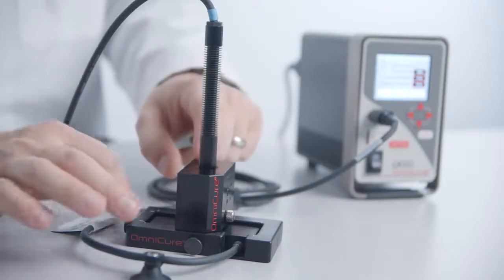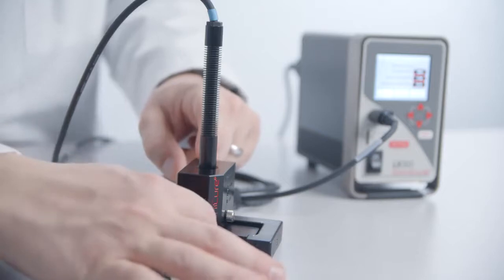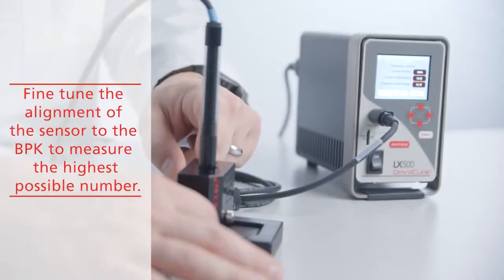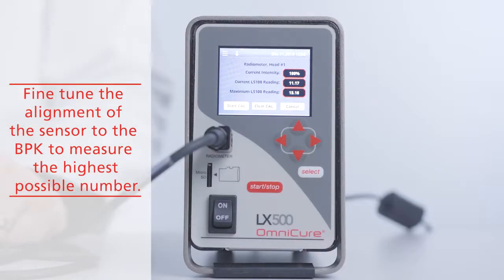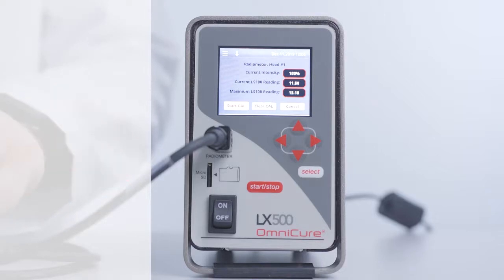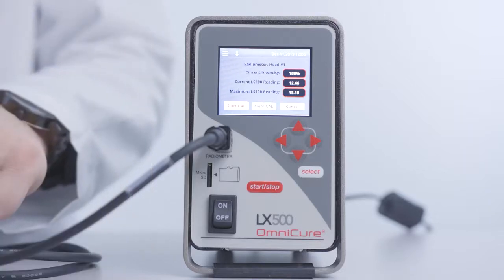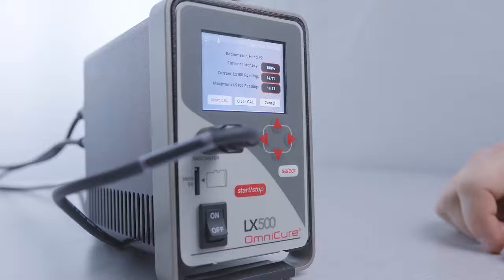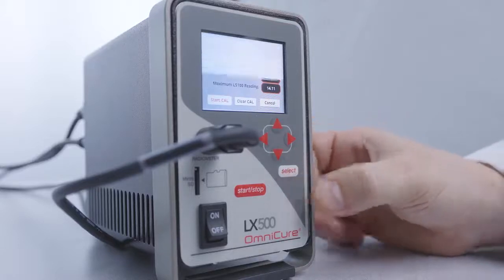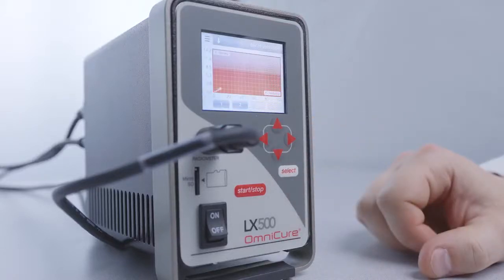Note that the irradiance measurement is a lot more sensitive than the power. Fine-tuning the beam positioning kit to sensor alignment to reach the highest reading is critical to achieve good calibration. Be aware that the highest reading may not be dead center, and position will be different from head to head.